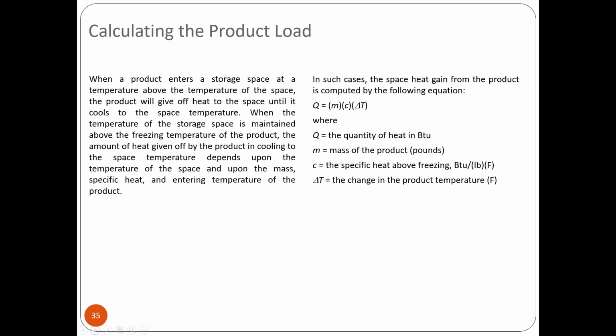So calculating the product load. So mga reviewers, when a product enters a storage space at a temperature above the temperature of the space, the product will give off heat to the space until it cools to the space temperature. When the temperature of the storage space is maintained above the freezing temperature of the product, the amount of heat given off by the product in cooling to the space temperature depends upon the temperature of the space and upon the mass, specific heat, and entering temperature of the product. So in such cases, the space heat gain from the product is computed by the following equation.